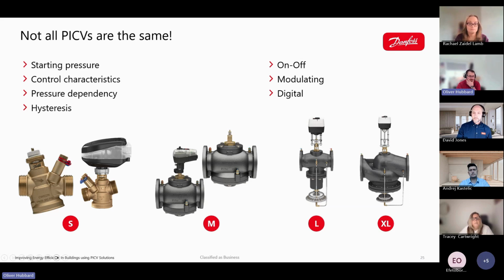So they're manufactured in DN15 to DN50, and there's a variety of different options when it gets to the actual valve, whether it's with high flow or low flow, internal or external threaded, with or without test plugs. There's about 30 different valve types across one small range. There's also flanged options as well, and even larger options here on the right hand side. And they all suit different actuators, so there is something for every different need within a building.